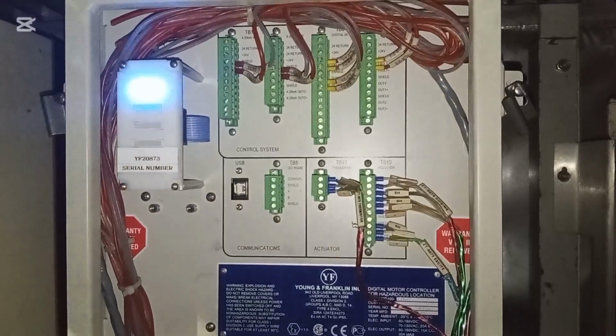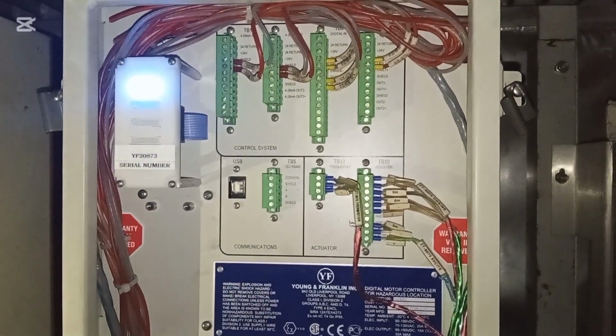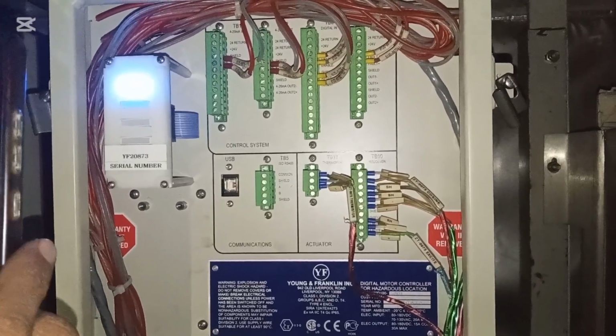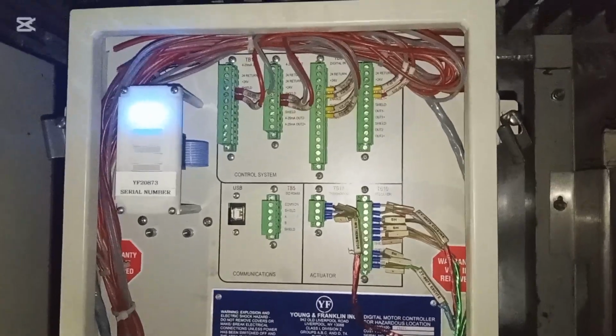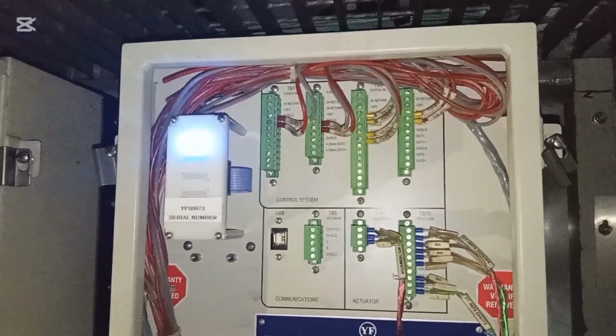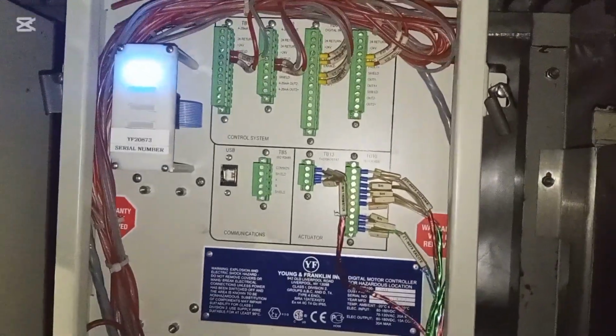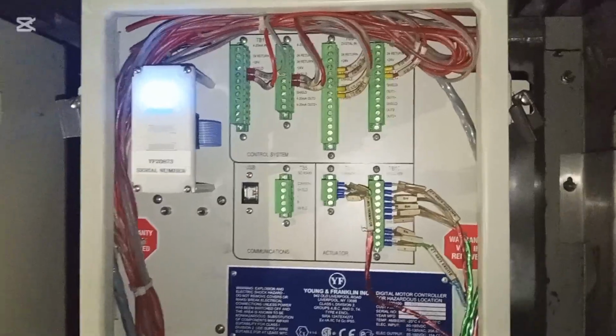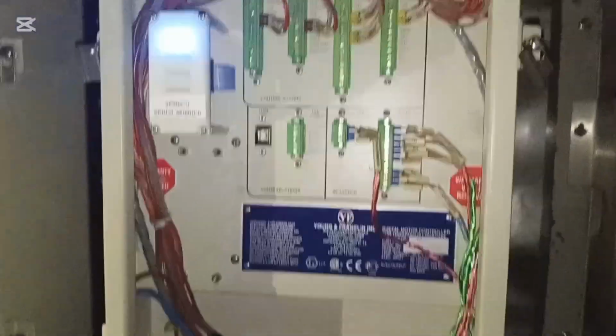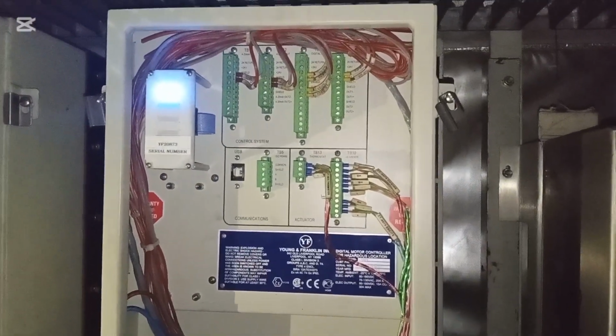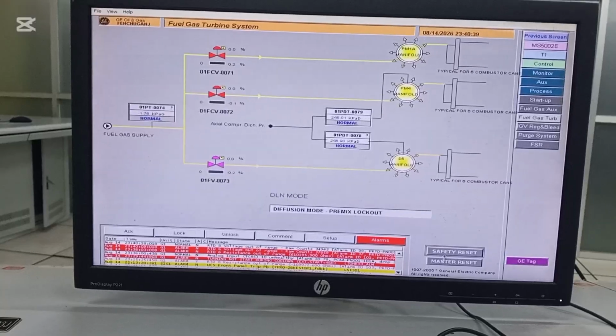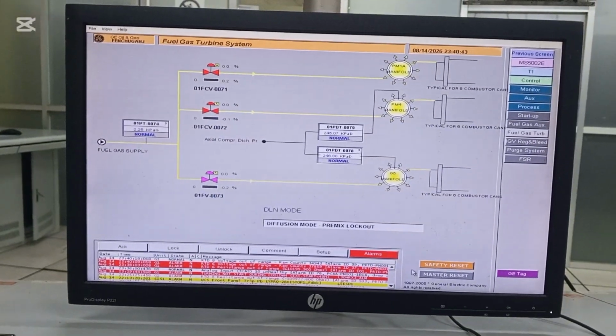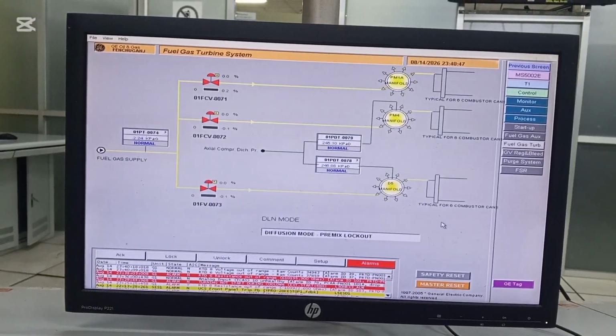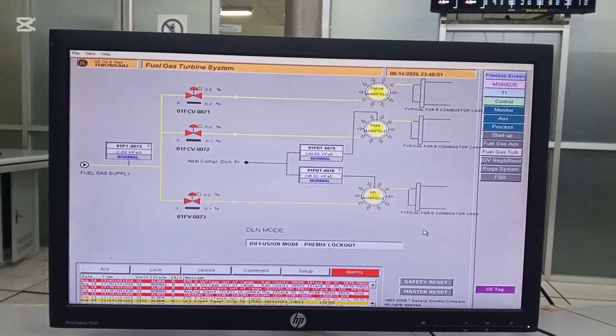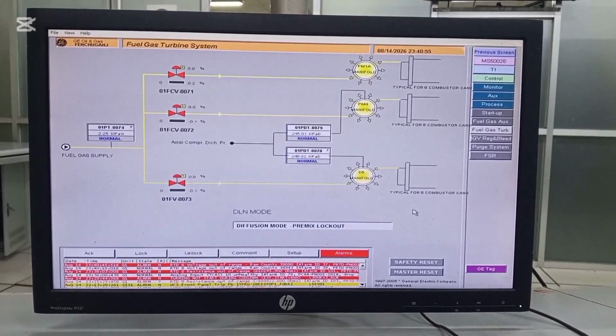Also, if the power fluctuates at any time, then this fault may come, and if this fault comes at any time, then at first we need to reset and check the power supply of the driver unit, that is the controller, which is 110 volt DC. If the power supply fluctuates or is disconnected and then becomes available again, this fault will come. Here after the reset, you see the valve color has changed and it came to a steady position. In this way we finally removed the gas turbine diffusion line valve driver fault.